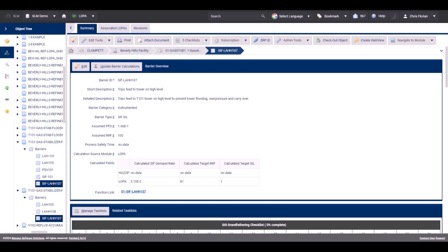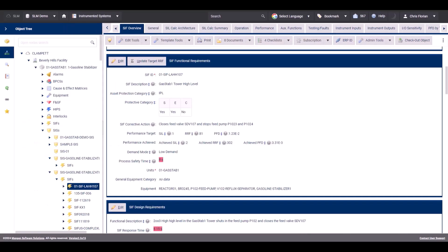In Instrumented Systems, the same information can be seen by clicking on the SIF object and viewed in the first section for the performance target SIL, RRF, and PFD. The target PFD is calculated as the inverse of the target RRF.